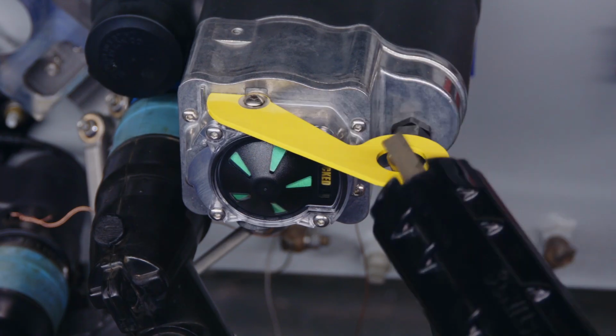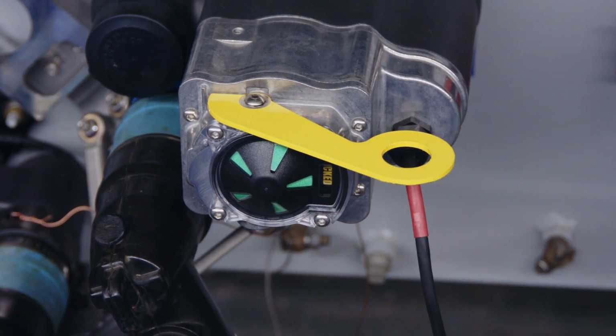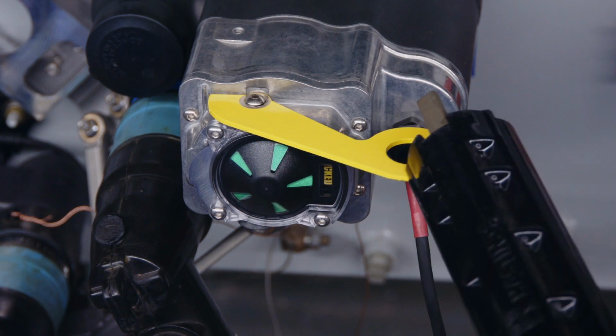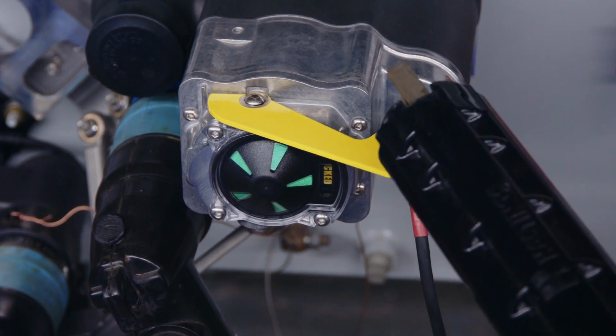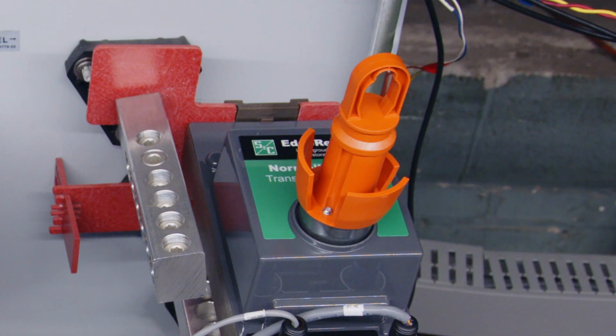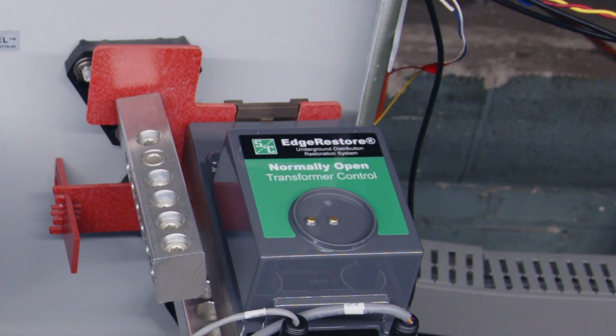Step 14. Open the normally open bushing well interrupter by pulling the lever forward once. Then push the lever once back towards the transformer into the ready position. Step 15. Remove the cordless power module.